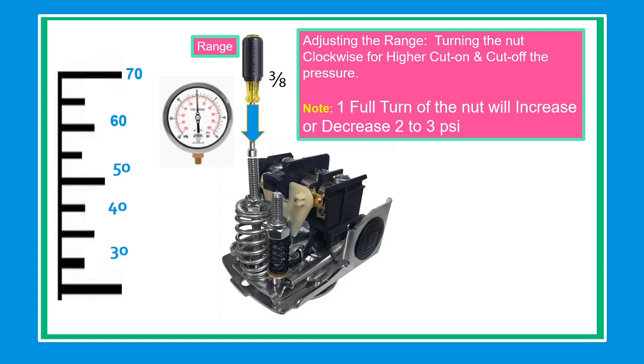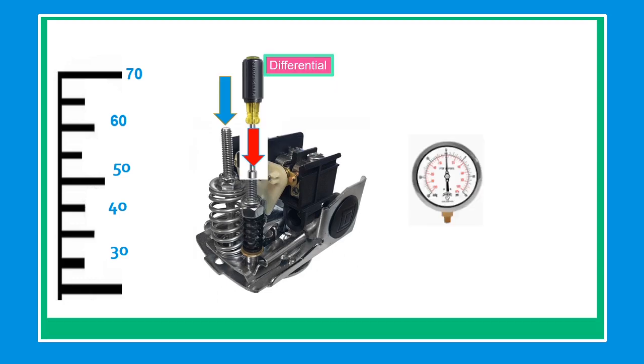The differential pressure adjustment is for cut out only. If you wanted your pressure to be 40 to 65 psi instead of 40 to 60, you could tighten the nut and that would adjust the cut out only.